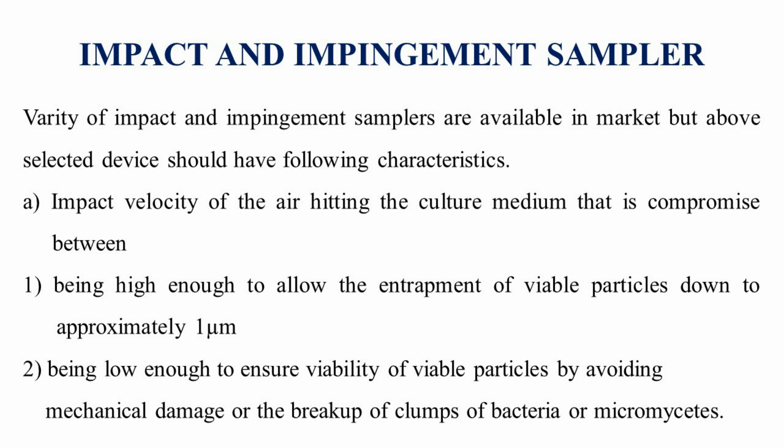In simple language, the selection depends on two characteristics. First, the sampler should be capable of trapping viable particles of minimum 1 micrometer. Second, the sampler itself should not damage viable particles at the time of sampling and should not cause clumping of viable bacteria or micromycetes.